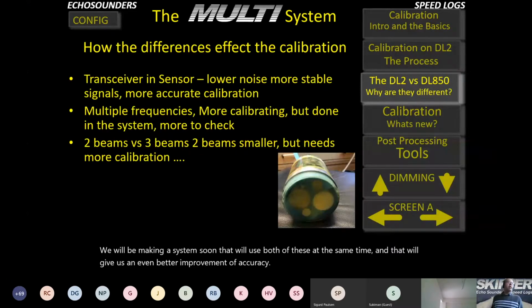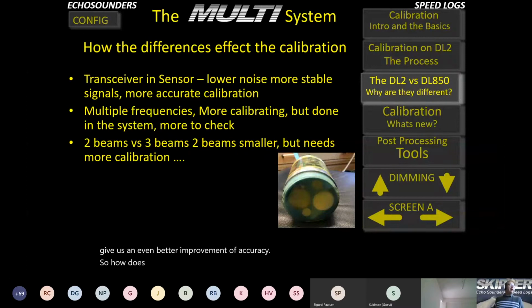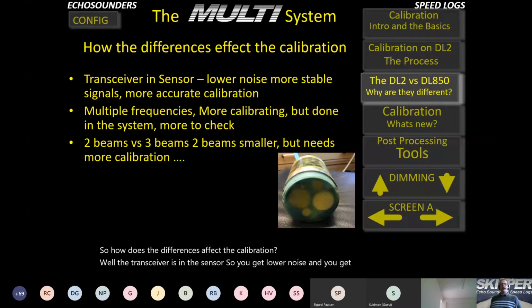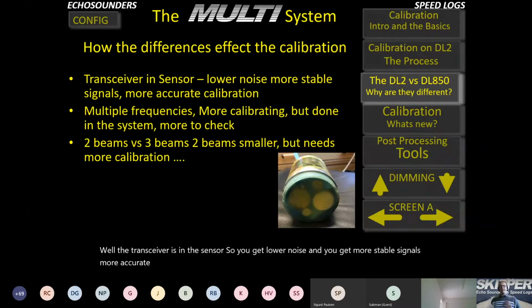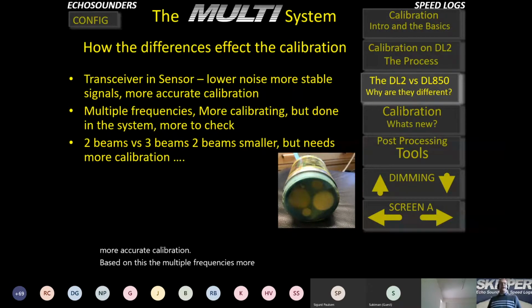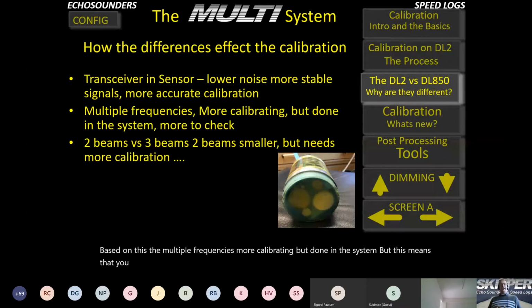So how do the differences affect the calibration? Well, the transceiver is in the sensor, so you get lower noise and you get more stable signals, more accurate calibration based on this. The multiple frequencies, more calibrating, but done in the system. But this means that you have more to check.